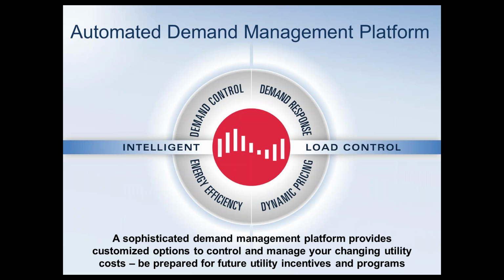So the demand management platform that Power-It has is a demand control, a demand response, dynamic pricing, and then energy efficiency. The demand control portion I utilized at Canon Muskegon for controlling my off-peak and my on-peak maximum demand set points. I utilized the demand response portion of the load control for responding to the brownout conditions automatically. And then dynamic pricing would be used in a market like California or places like that that have a floating marketplace. And then the energy efficiency is an operation where they can go in and trim VFD drives and things of that nature, and it's used primarily in refrigeration and freezer applications, which is the other side of Power-It's platform that they support.